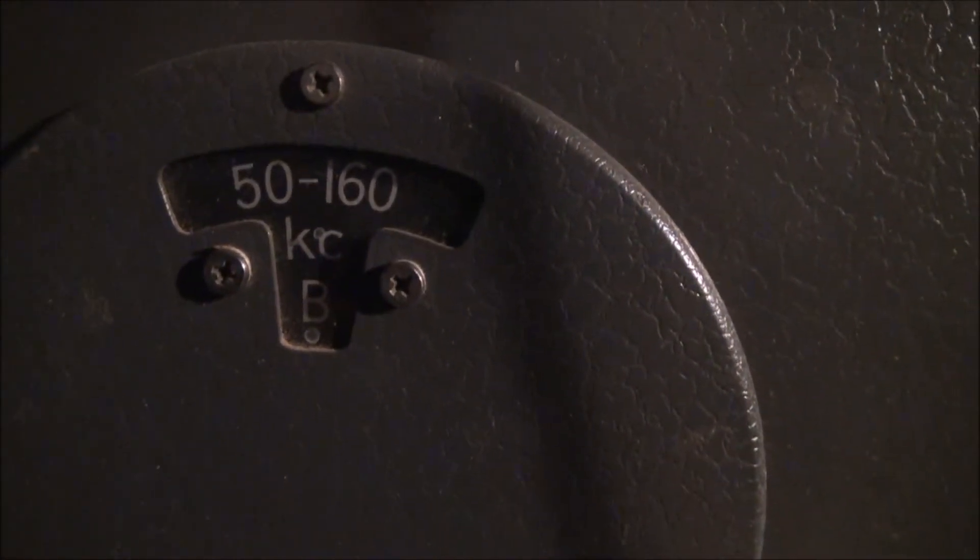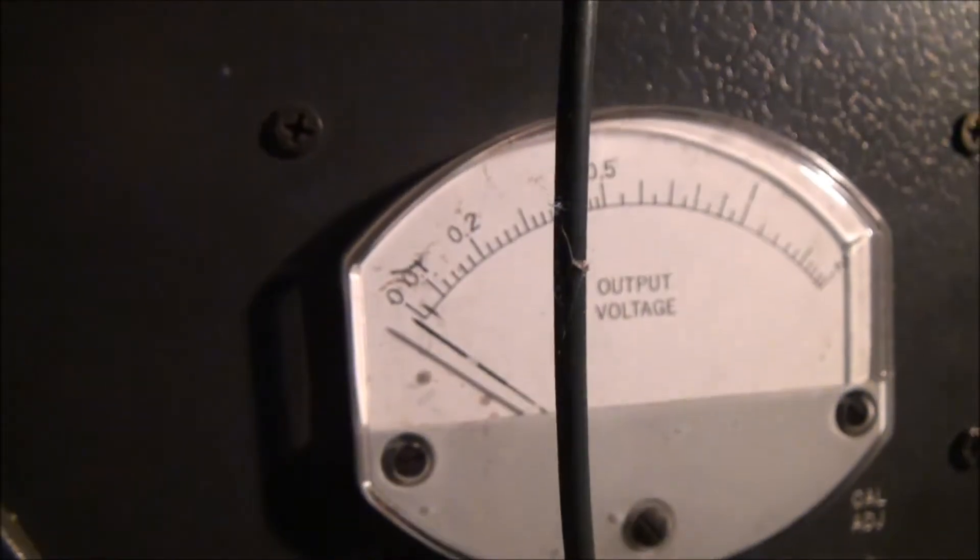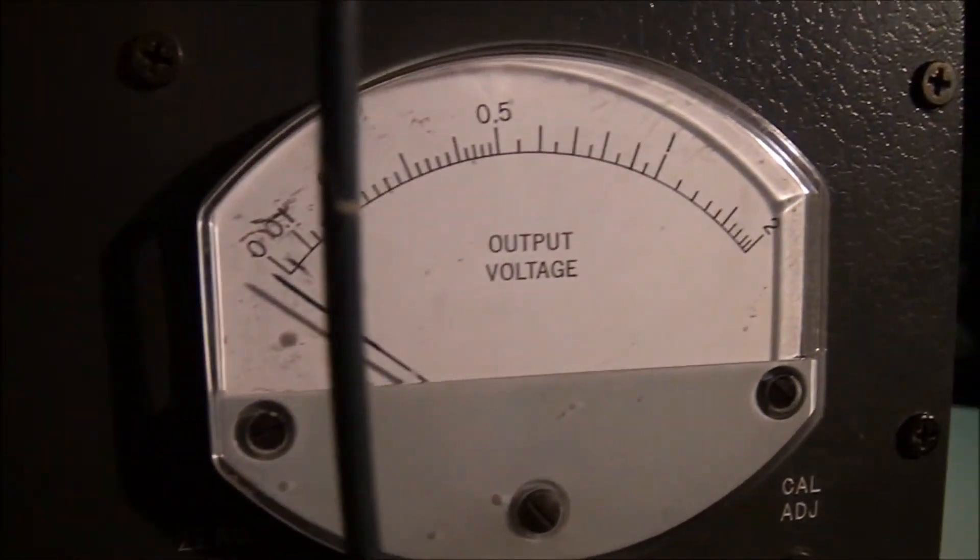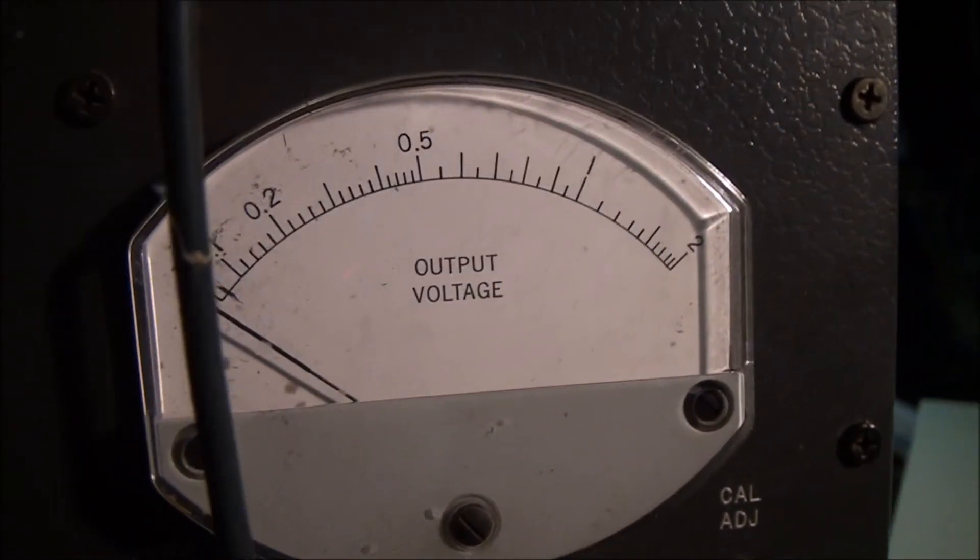What I did find is a couple of ranges not getting any output at all. On the 50 to 160 kilocycles and the 16 to 50 kilocycles, there's no output going on at all with it. So it's probably a fault in the instrument, something that needs to be checked out. But all the rest of the ranges seem to be working with reasonable accuracy.